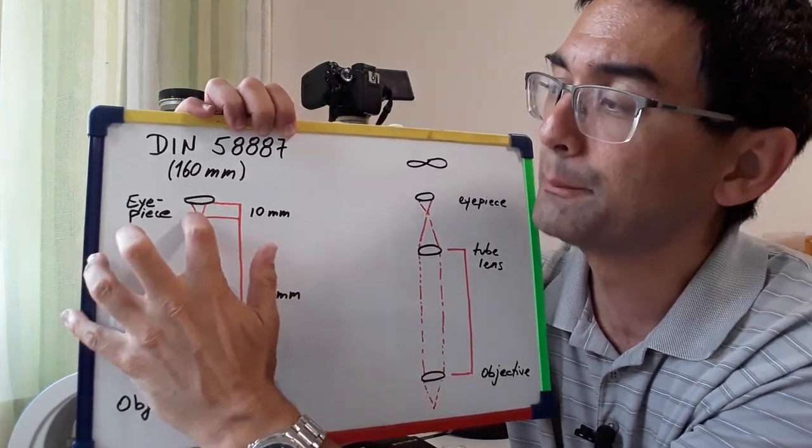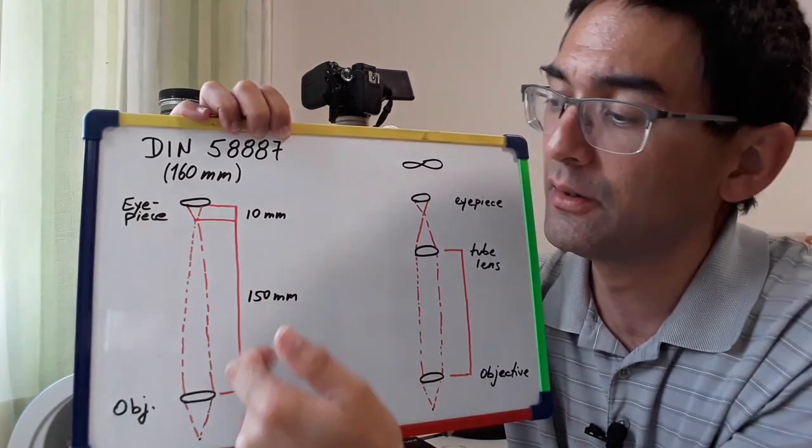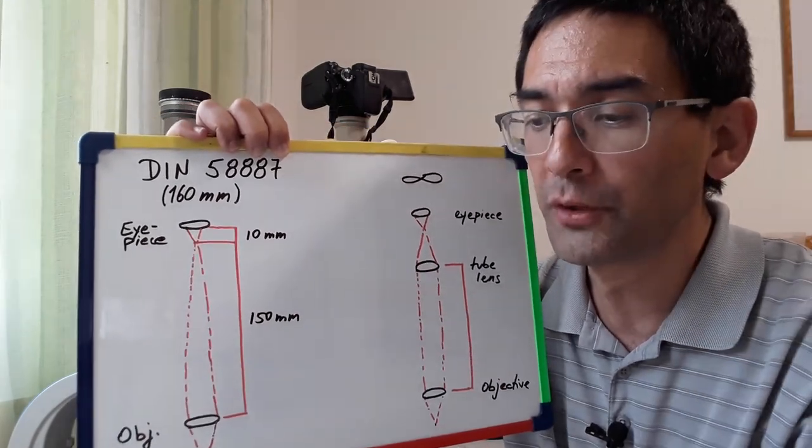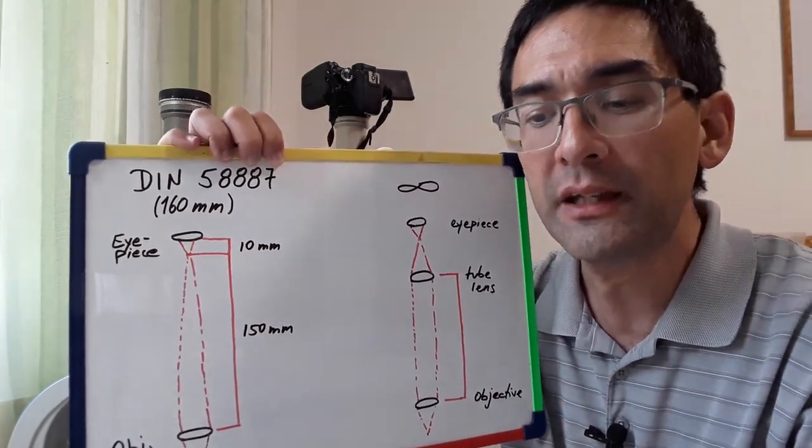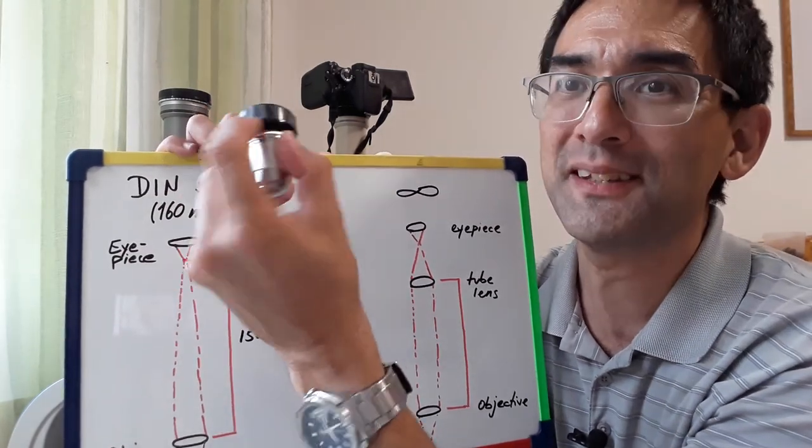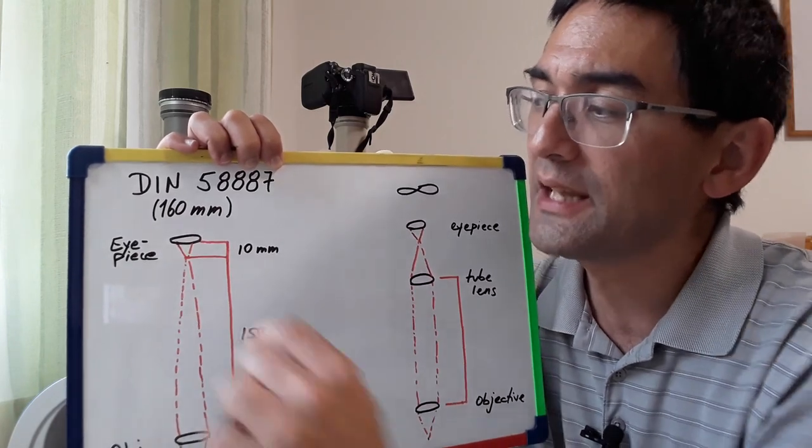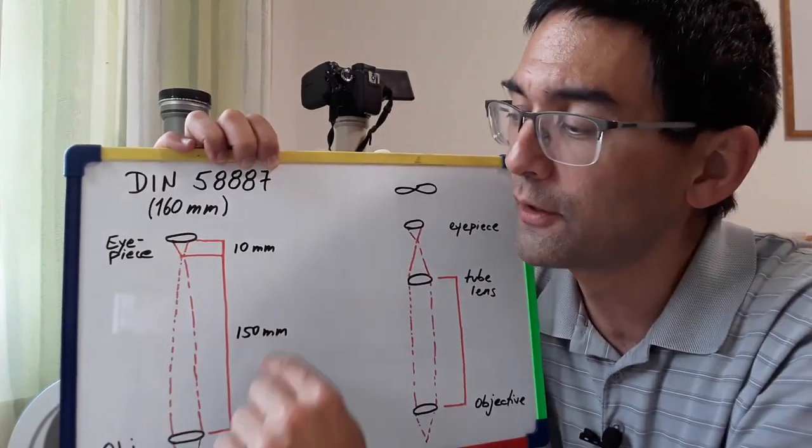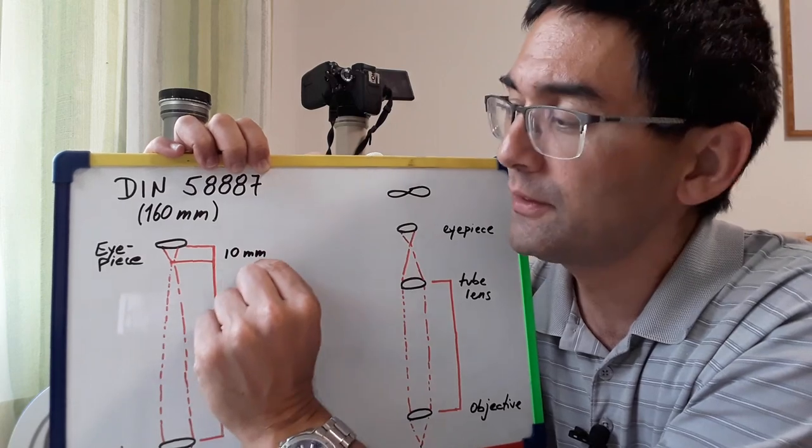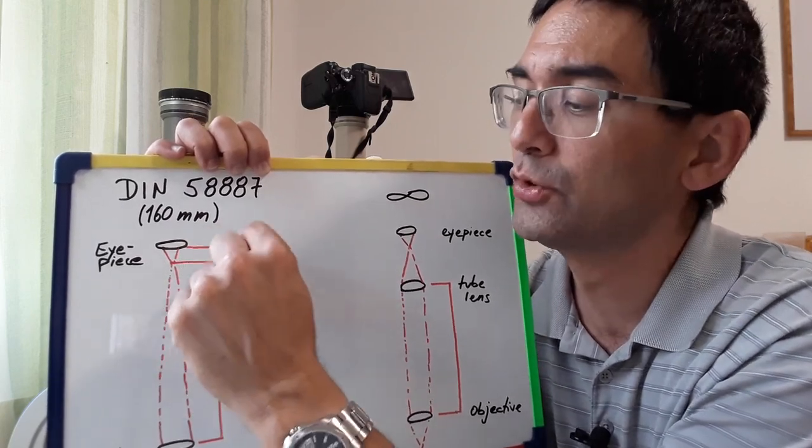So that is basically the projection plane. It's from the top, you have to always go from the top of the objective, so this is basically where I've got the plastic cap now. From the top of the objective to the place where it actually creates the image inside the microscope is 150 millimeters and then you have an additional 10 millimeters where the eyepiece rests.